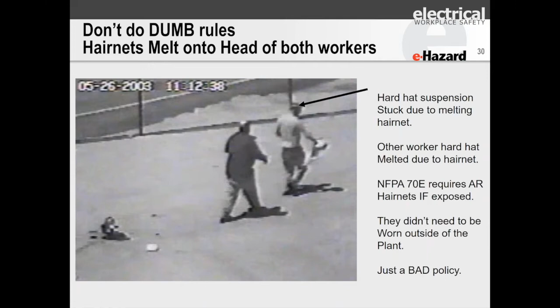Hairnets and beard nets, there's a Nomex hairnet here on the left. The polyester hairnets are on the right, and it melts and drips, and that's why the standard requires that if you're wearing hairnets and beard nets exposed to arc, you should be using one that's actually arc rated. High-vis vests. Again, we have a high-vis vest that was burning. Those say they're flame resistant.